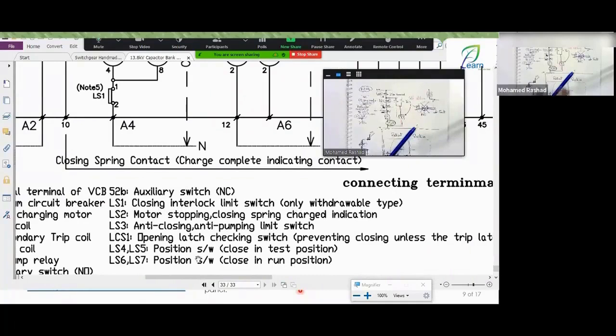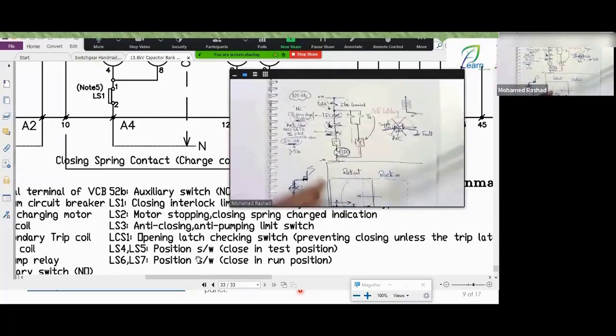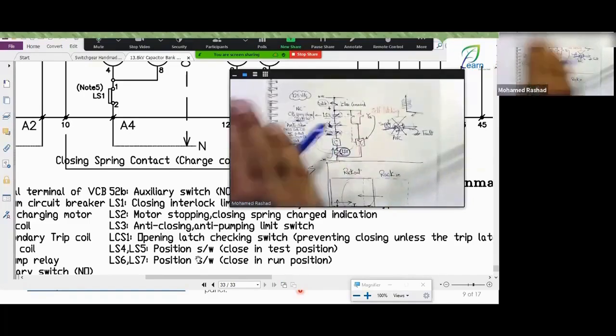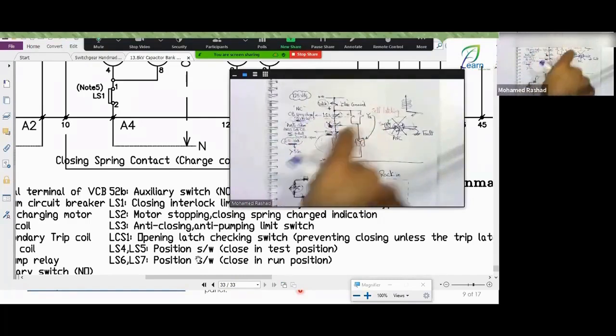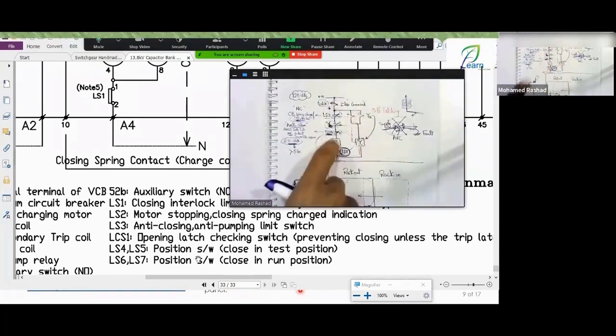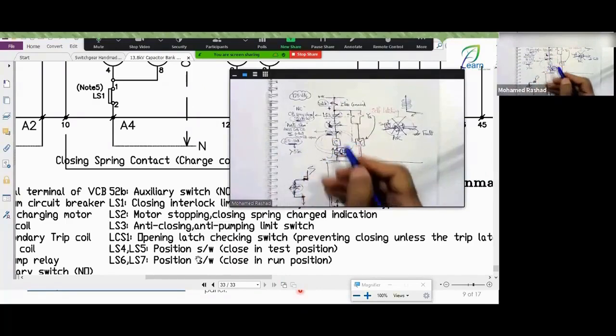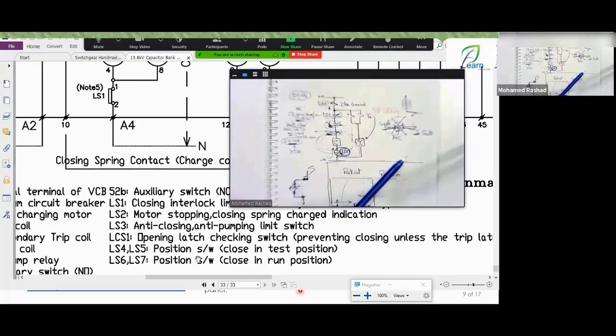It means that if the breaker is not totally racked out or totally racked in, this limit switch opens to cut the negative path to the closing coil. Therefore, even if you give a close command, it won't burn the closing coil. Mechanically, the breaker might close, but electrically, if you keep applying DC to the closing coil, it will burn. That's why if the breaker is neither totally racked out nor totally racked in, the limit switch opens to prevent the closing operation or connecting the DC to the closing coil, so that the closing coil doesn't burn.